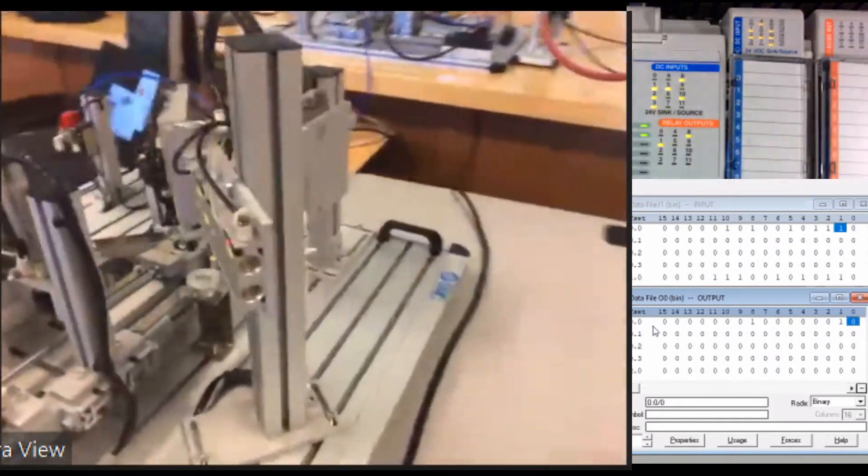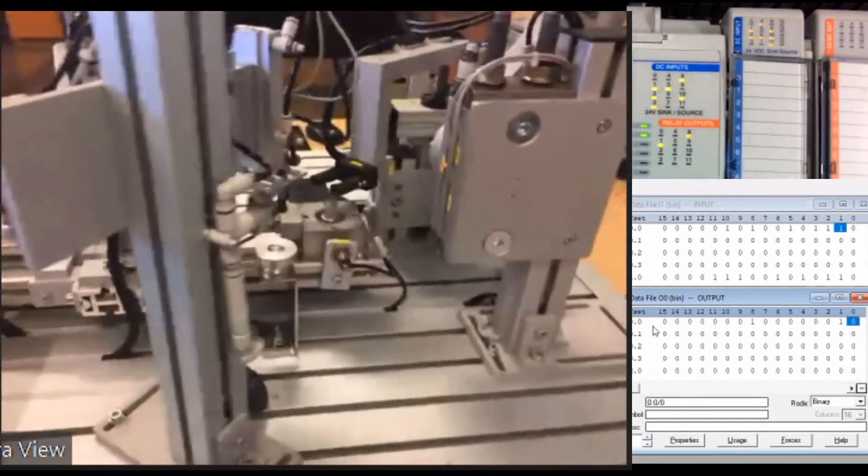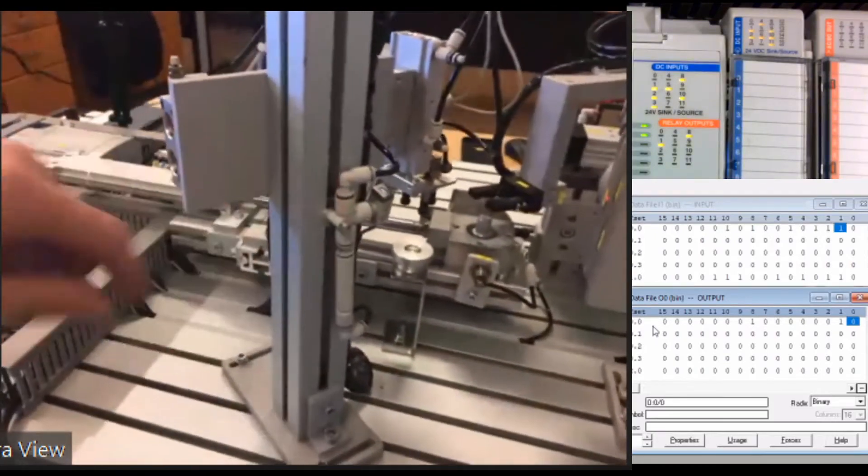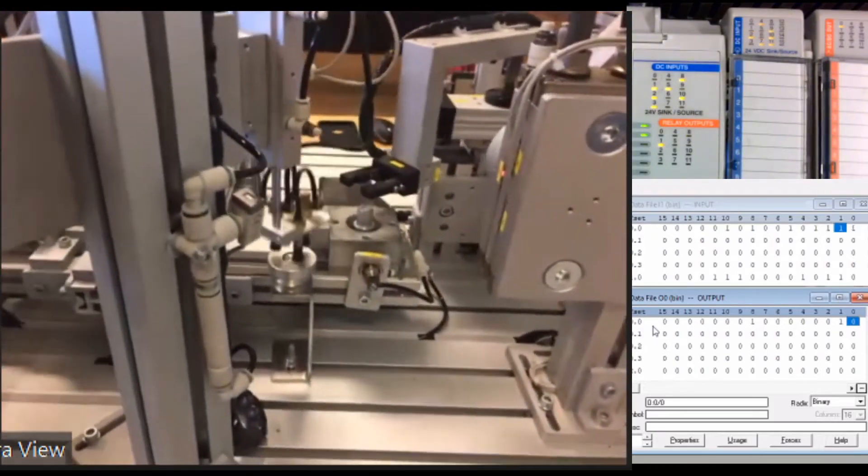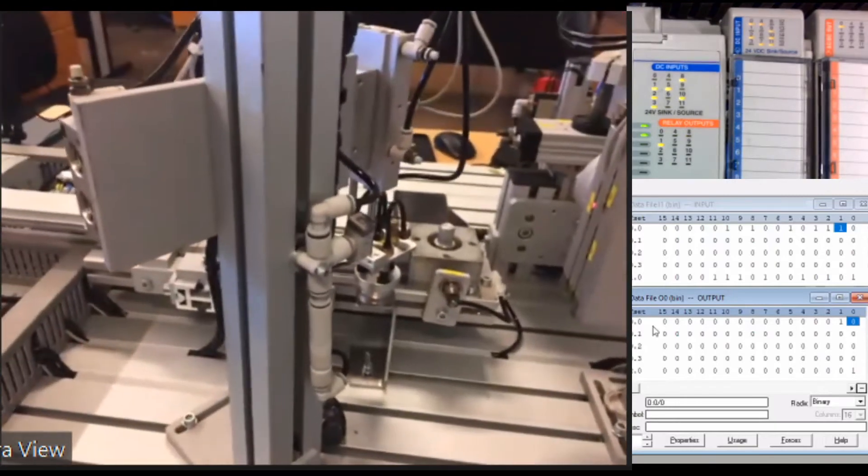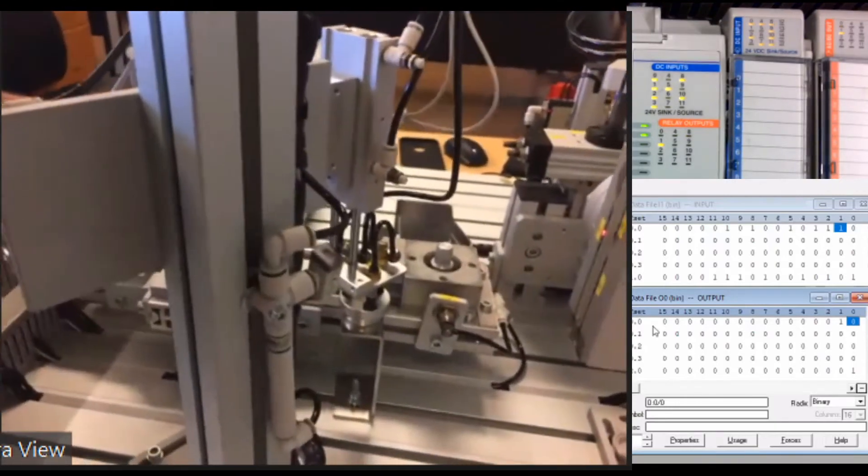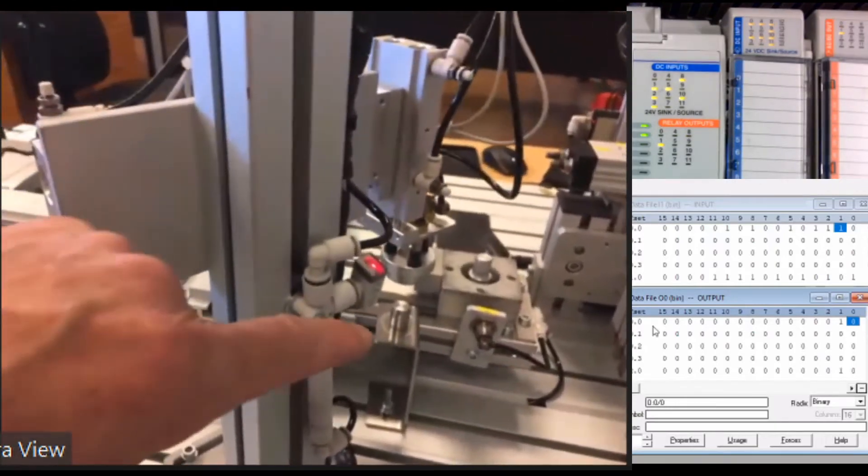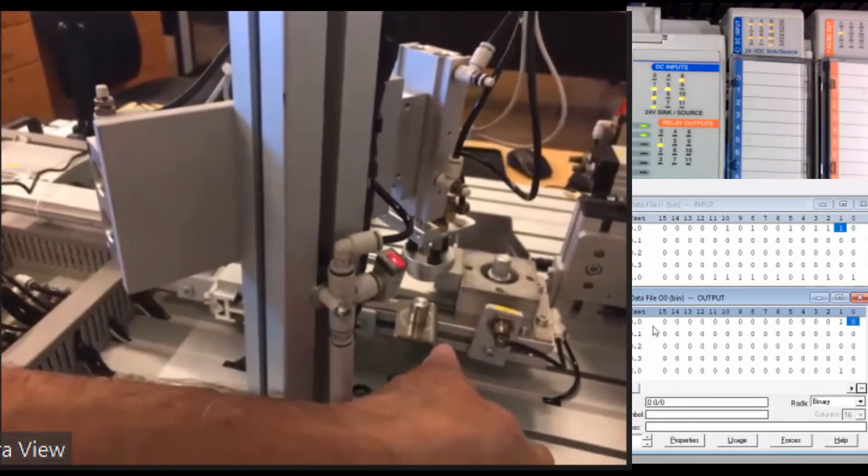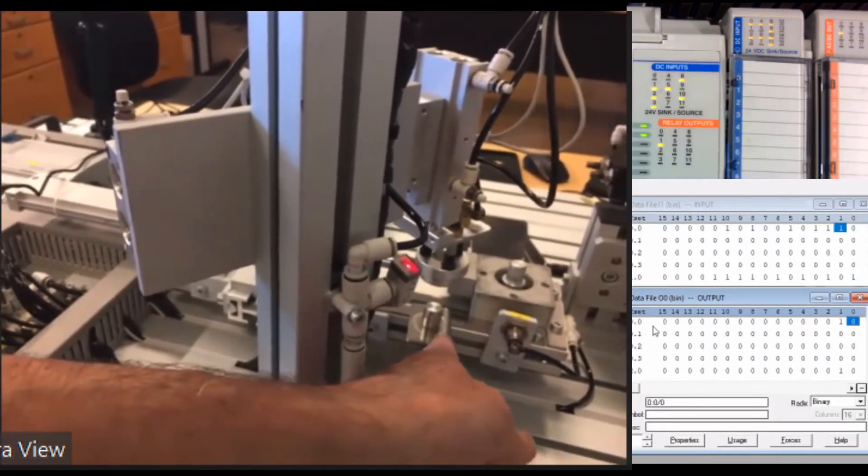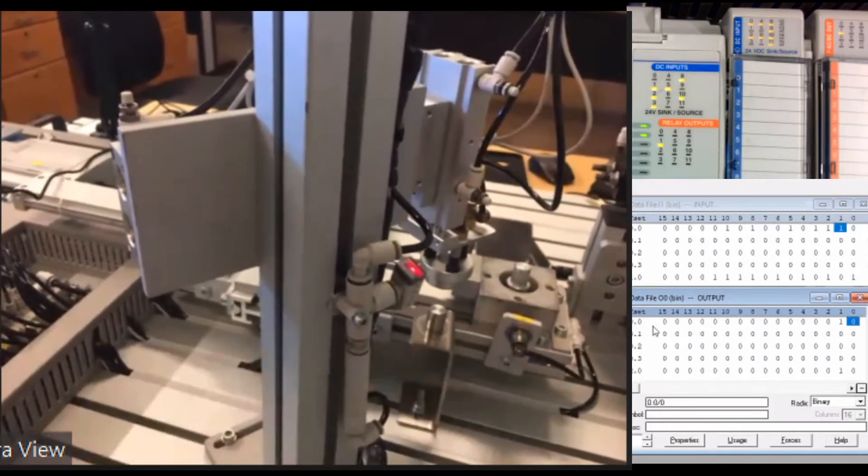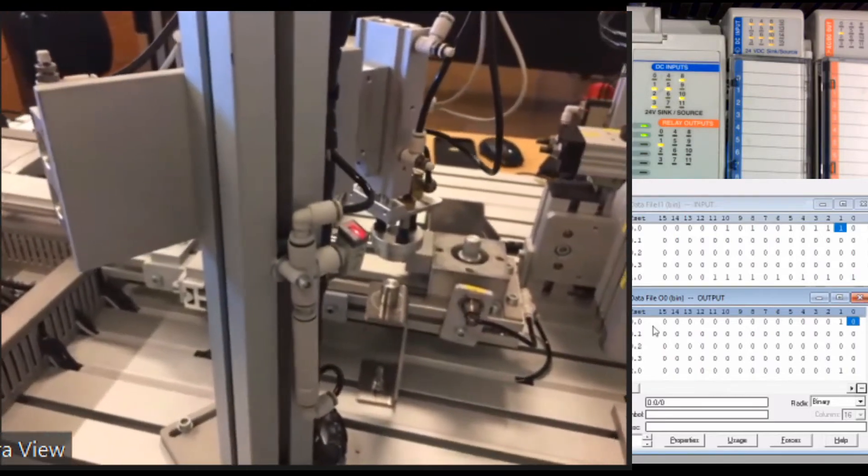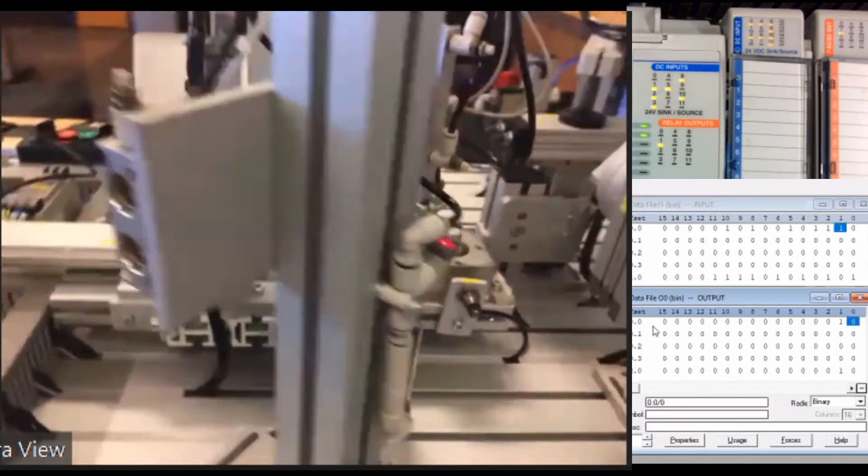I'm going to try to change my angle here. I've got to keep pushing this button here. So we're going to start up the vacuum part here. So now that I'm back here, you can actually see the vacuum kick on. So you'll see that it did form a vacuum. As soon as it went down, it had that vacuum. And so it came up, and that's how it knows that it actually has the part, because if it didn't have a part, it wouldn't be forming a vacuum.